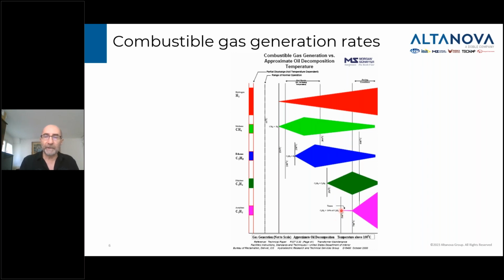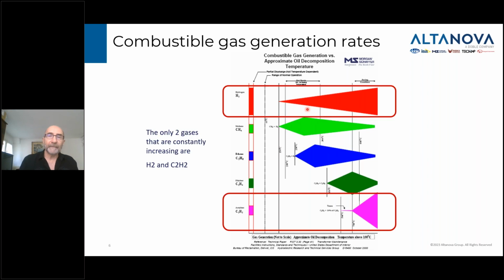And between 500 degrees and 700 degrees, the rate of generation of acetylene is very, very small. So usually, when you start seeing acetylene appearing in your DGA, when you're still seeing 1, 2, 5 ppm, you're usually in this area. As soon as the fault temperature increases over 700, that's where you will see the generation of acetylene accelerate. And this is where you get into an area of potential failure of your transformer, because you have a huge amount of acetylene being generated at the same time that a very large amount of ethylene is being generated.